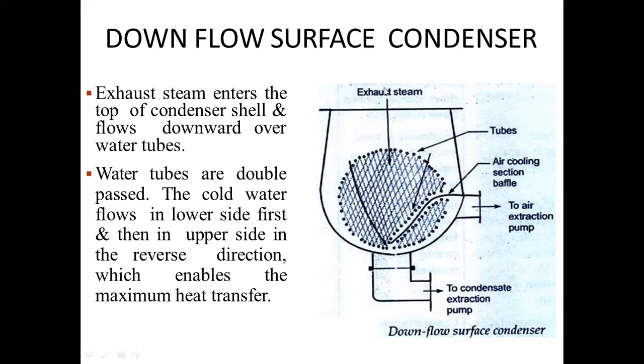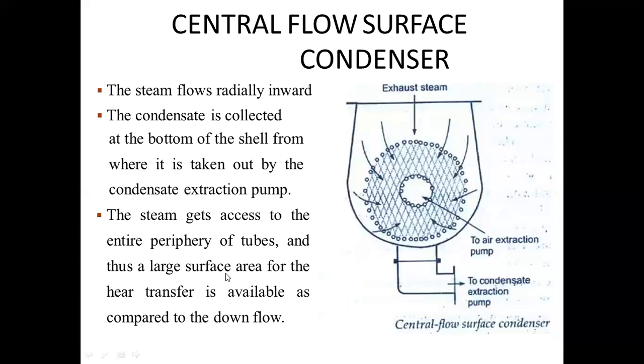So here we are supplying exhaust steam from the top side, and after releasing its heat, the condensate can be collected from the bottom, and air can be removed with the help of an air extraction pump from the side of the wall. Exhaust steam enters the top of the condenser shell and flows downward over water tubes. Water tubes are double passed. The cold water flows in the lower side first and then in the upper side in the reverse direction, which enables maximum heat transfer.